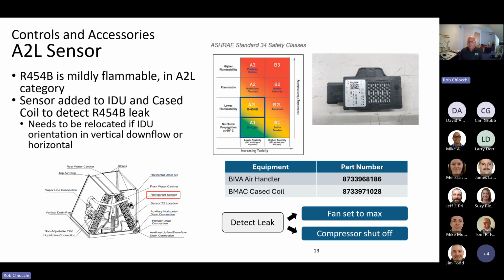As I said, the sensors will be pre-installed on the coils. There will be a tether wire that will need to be connected to the furnace circuit board for the system to work. What this will do is, if it detects a leak of the refrigerant, it will render the outdoor unit inoperative and turn the main indoor circulating blower on until the leak level goes below a certain point. Once the leak level gets below a certain point, the system will resume normal operation after a test period.